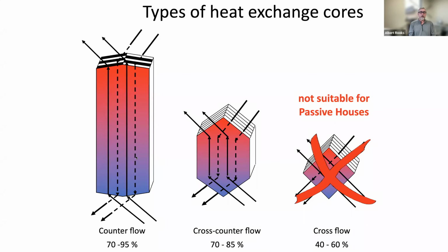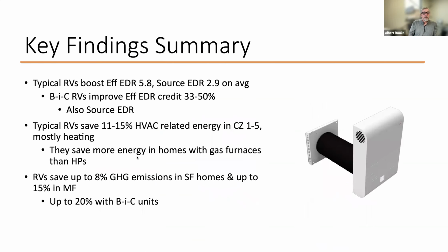And so if we think about that little tiny square on the right where it says not suitable for passive houses, that's kind of when we talk about a passive house. You can't really do that much transfer in that short of a distance in that kind of a shape, right? Because as soon as the airflow comes in from the upper right, it very quickly crosses over that core, it doesn't get a chance to pick up much energy or much enthalpy, and then out of the building it goes. So on the extreme left, if you lengthen that whole cycle and the 2 streams of air spend more time in proximity to each other, you get better transfer. So, there's some notes that explain that a little bit more.